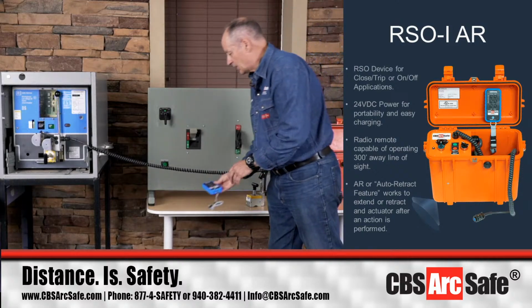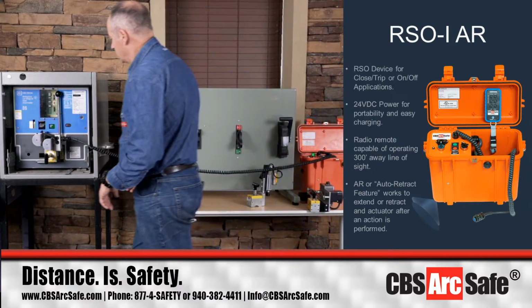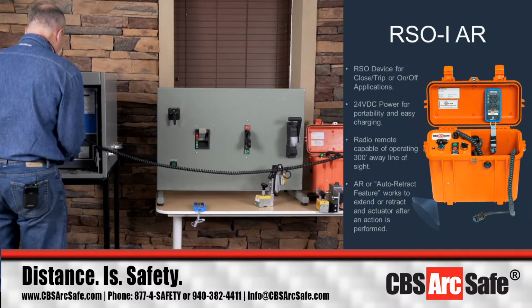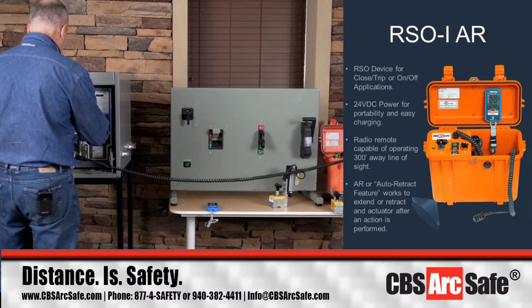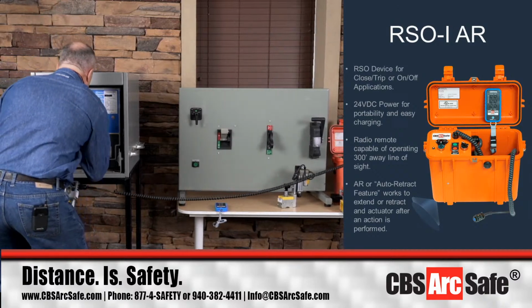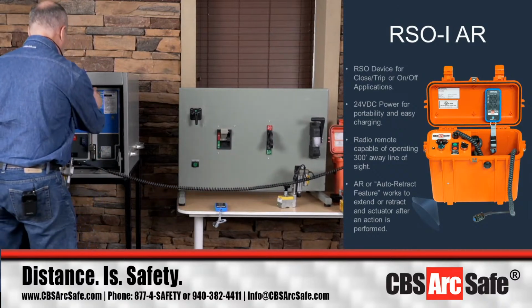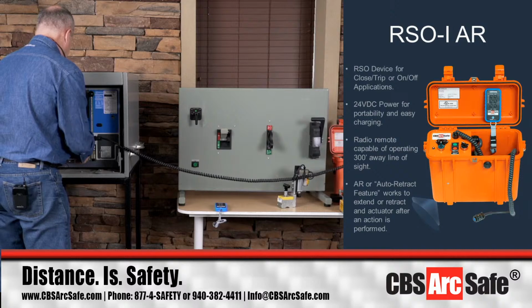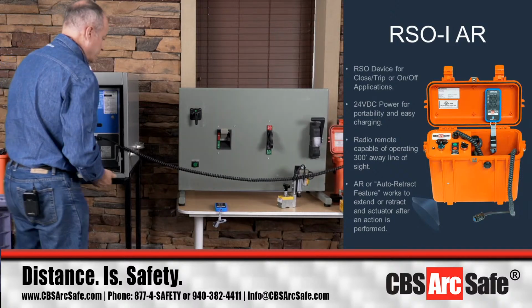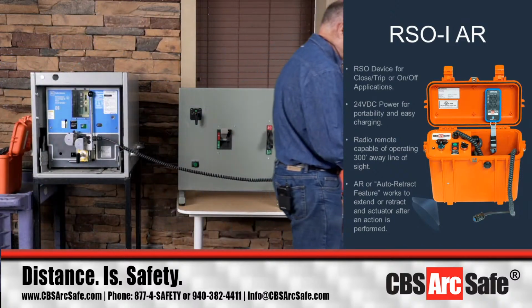Since this actuator is not capable of charging the breaker, I'm going to take this off and charge it. I'll place it back on there, and this time I'm going to use the wireless remote to close and trip the breaker.